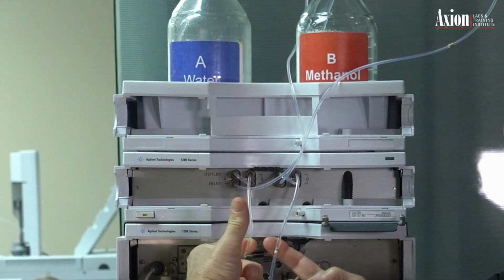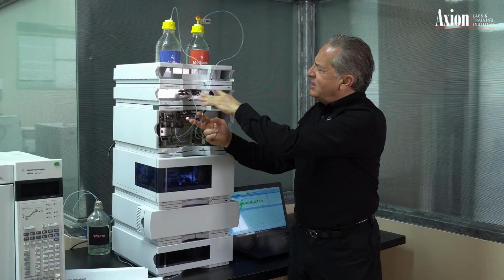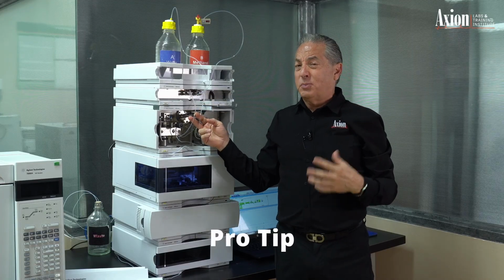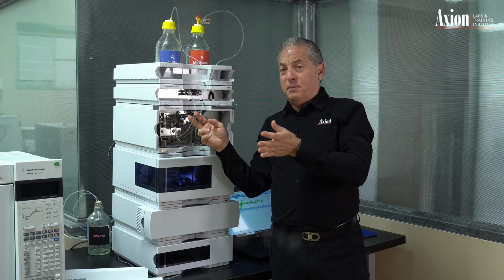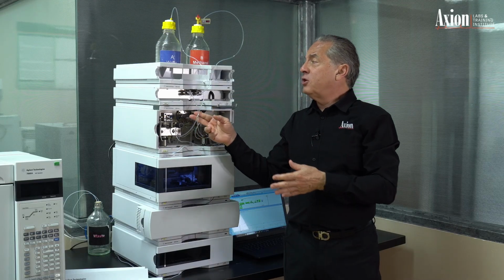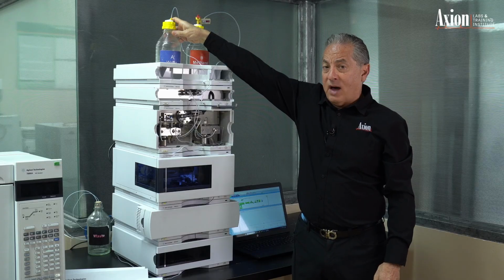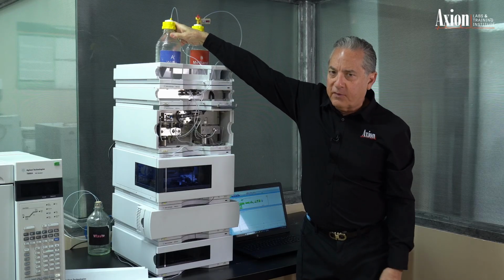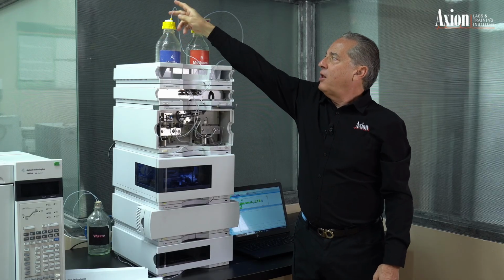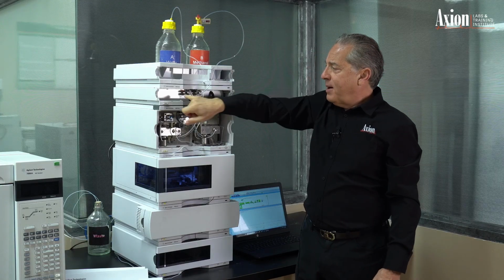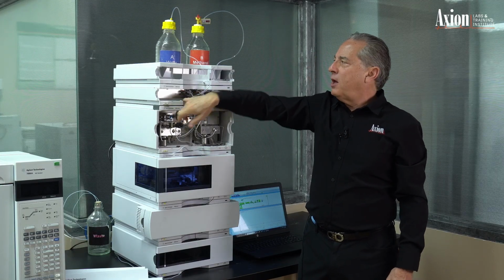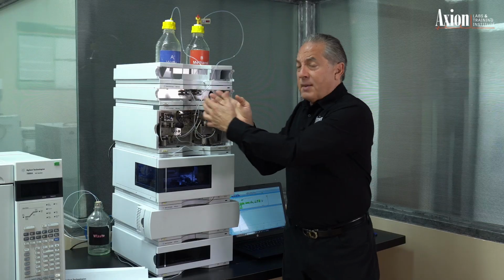They've gone through degassing. What you can't see behind the scenes is that in this version, there's 1 to 2 milliliters per channel behind the scenes. So if you ever change your A bottle, if you go from a phosphate buffer to an acetate buffer, remember, not only do you have to pump out the lines, but you've got to pump out the volume that's inside there as well. Okay, so now we have come out of the degasser.